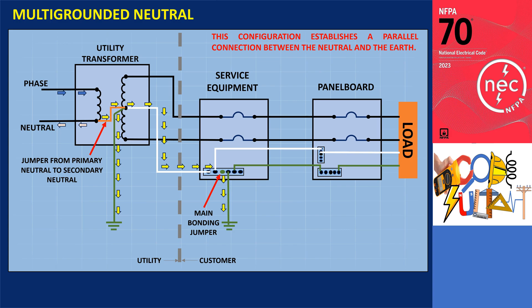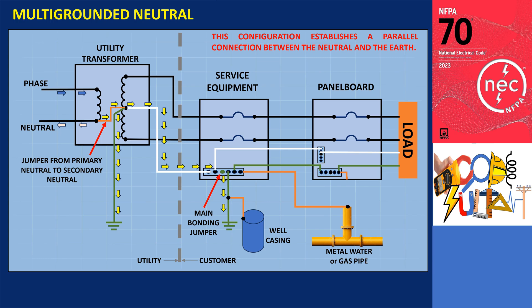It is important to note that according to section 250.4, the equipment grounding conductor must be connected to non-current carrying conductive material that is likely to get energized. In the presence of a well casing and metal pipe, it must also be connected to the earth, creating an additional pathway to the ground.